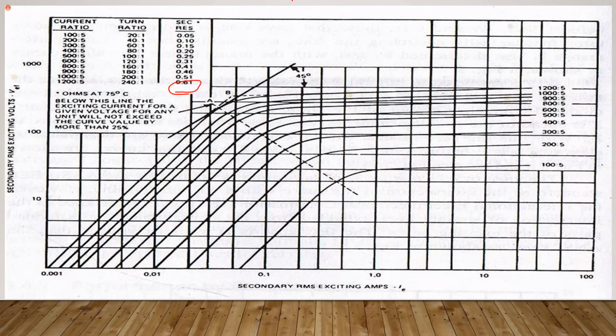Question? Yes, sir. I don't really understand the 2400 to 10, because if you have 100 to 5 and then you have 200 to 5, why would you multiply the 2400 by 2? No. What I'm saying, listen carefully, is that on the 1200, remember this is a multi-tap. So you can use one of the 10 taps available. So if you are using the 1200 to 5 tap, you with me? If you are using that one, and 2400 amperes is passing through, then you'll get 10 amperes on the secondary.